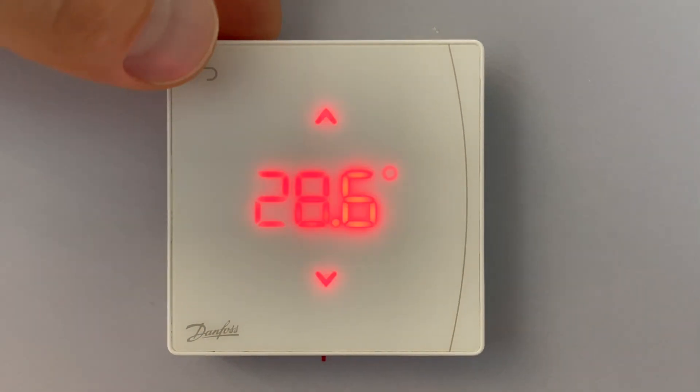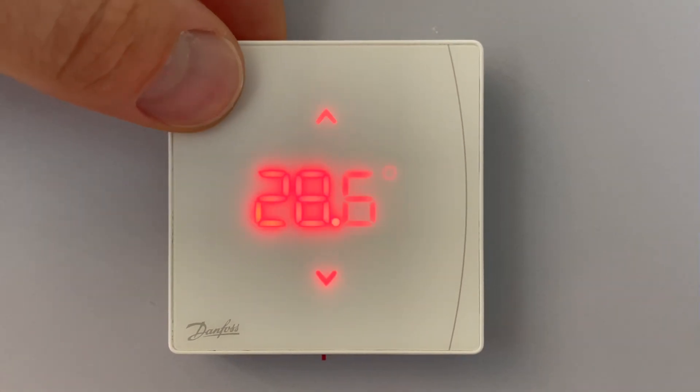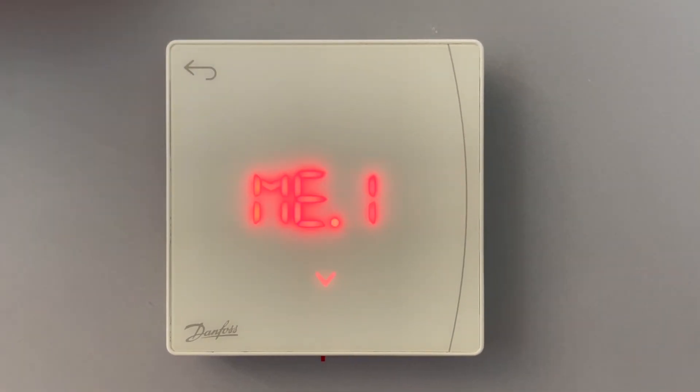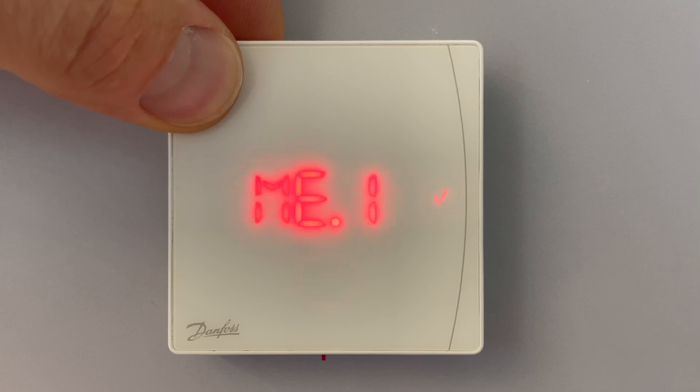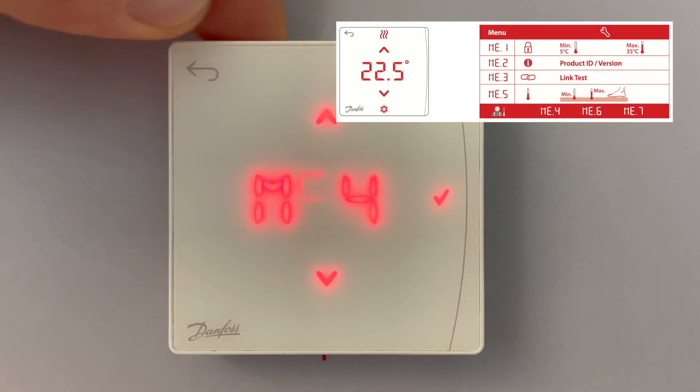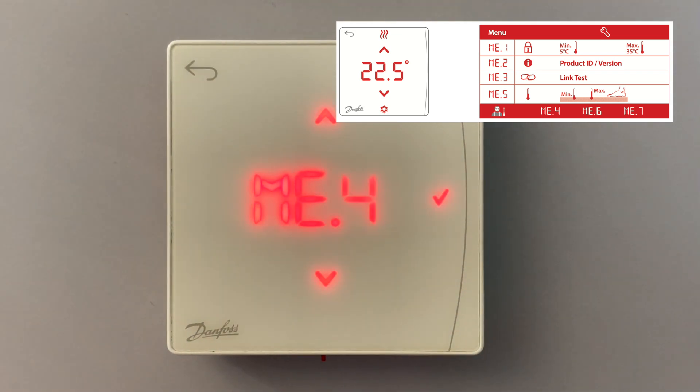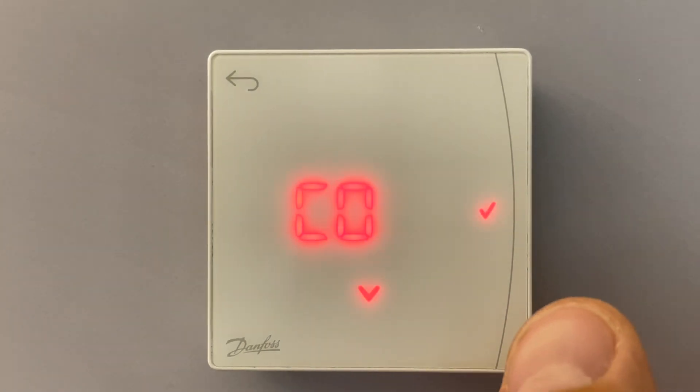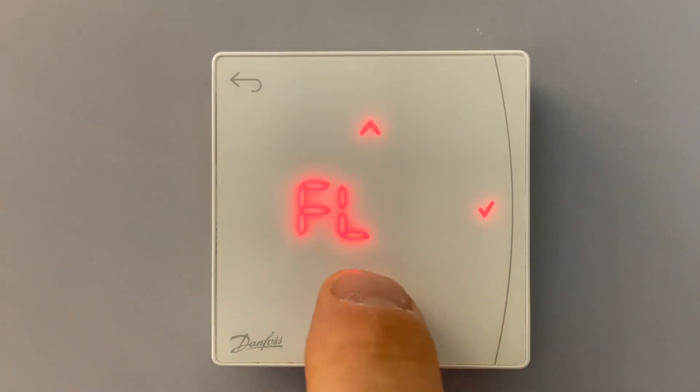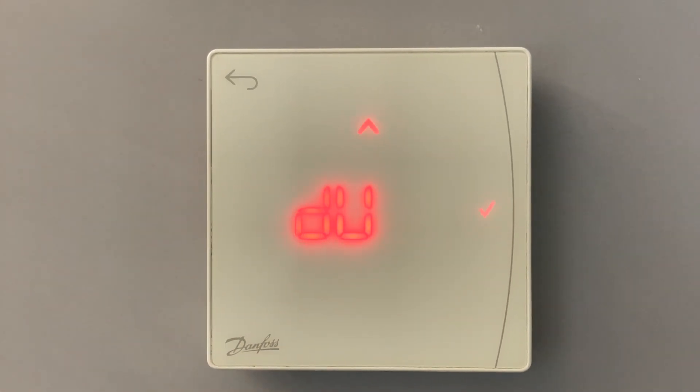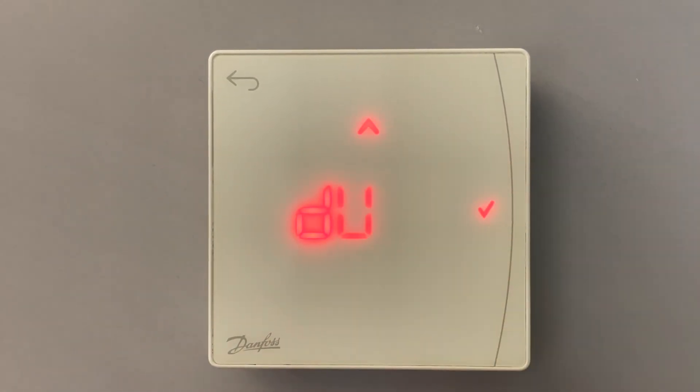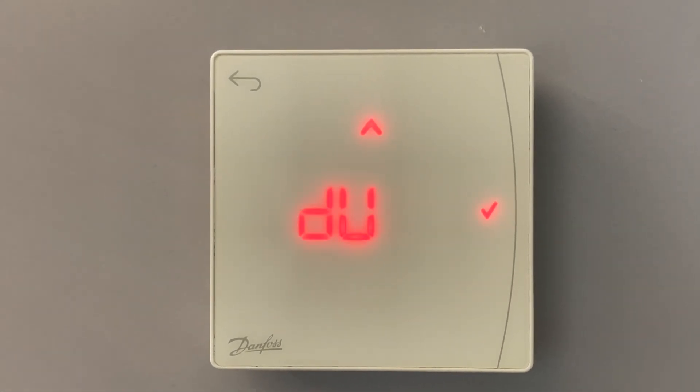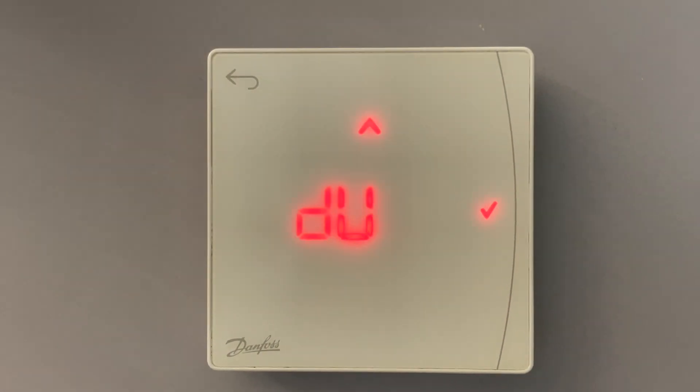For entering even deeper menu we need to first go to the first stage of menu and then, being in this menu, again push and hold for 3 seconds. We will enter even deeper menu. This is menu four where I can choose combined mode, floor mode, and dual mode. So choosing dual mode means I have in one room radiator and floor heating.